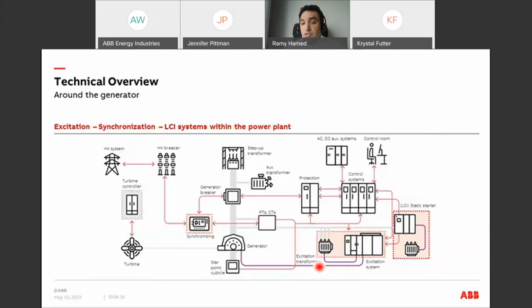Some of the other applications for the LCI would be synchronous condensers. For example, for HVDC lines, at the end of the HVDC line, we need a synchronous condenser to be able to provide reactive power. One of the other applications of the LCI is pump storage. So in pump storage, we need to either pump or generate depending on the time of the day. And then the generator in the plant will work as either a generator or a pump. And again, to work as a motor, we need a variable speed drive. And in that case, it's the LCI that is used with the synchronous motor.